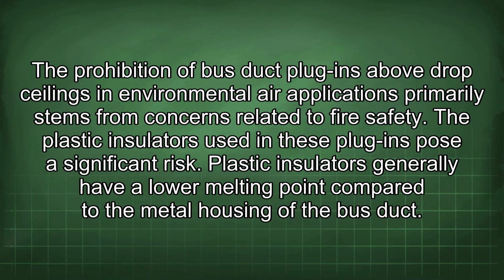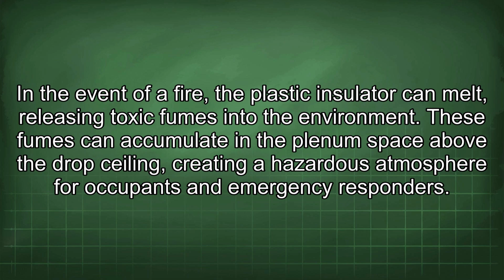The prohibition of bus duct plug-ins above drop ceilings in environmental air applications primarily stems from concerns related to fire safety. The plastic insulators used in these plug-ins pose a significant risk. Plastic insulators generally have a lower melting point compared to the metal housing of the bus duct. In the event of a fire, the plastic insulator can melt, releasing toxic fumes into the environment.